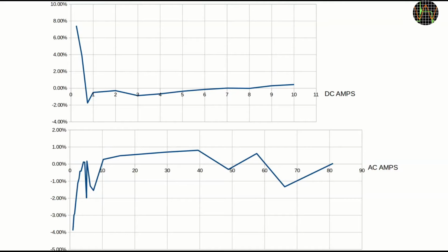A quick look at the amps. The lowest range on the KC602 is 60 amps. It is simply not meant for electronics, so it's no wonder that it struggles below 0.5 amps. From then on it's okay. On AC it's exactly the same story. You can't use it to investigate the small earth leakage currents that can cause nuisance tripping on RCDs or GFCIs. There are special clamp meters for that, and the KC602 isn't one of them.